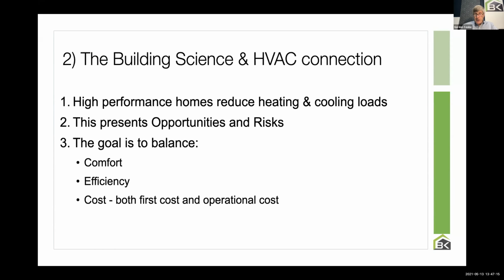There is virtually no difference between the price of a 50,000 BTU and a 75,000 BTU furnace. I get that. That's not the issue. But there is a cost difference in the ductwork that you have to hook up to a 50 and a 75. A 75,000 BTU furnace moves more air. So now the ductwork has to be bigger. The grills have to be bigger, and so on. And so there's cost there, and there's space concerns. The real cost in equipment is in air conditioning mode. It's $500 a ton or more than that, perhaps. $500, maybe half a ton, to get a bigger air conditioner. So keep that in mind.